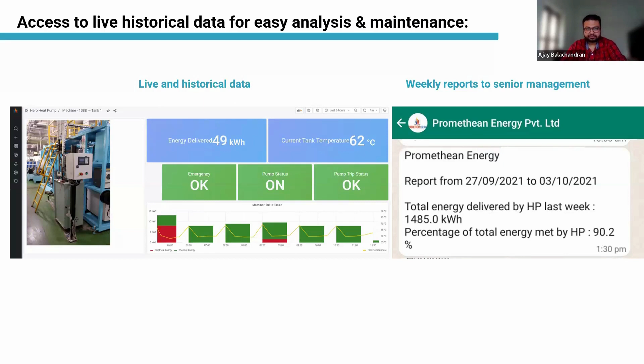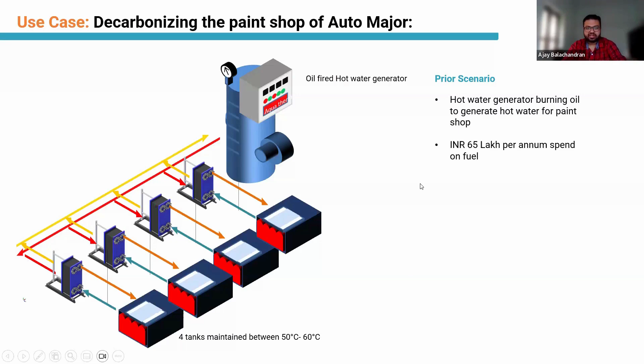They were using fuel oil to heat the hot water generator and ran it continuously. We audited the plant and found multiple air compressors. We installed heat recovery systems to recover the maximum heat available, and for the remaining heat required, we installed a couple of heat pumps. With the heat pumps and heat recovery system, the company was able to cut down the working of the hot water generator, reducing the carbon footprint by 90%.